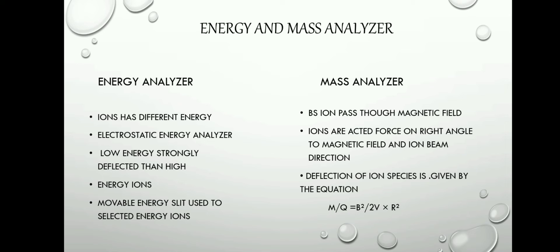Now let me explain about the energy analyzer and mass analyzer. Energy analyzer: ions have different energies. In an electrostatic energy analyzer, low energy ions are more strongly deflected than high energy ions. A movable energy slit is used to select energy ions.